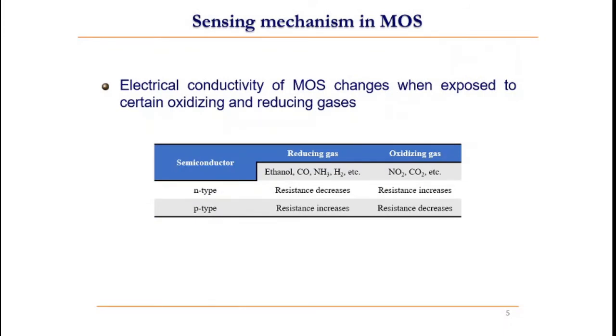When a metal oxide semiconductor is exposed to a gas, its electrical property changes. And this property depends upon the type of semiconductor. If the semiconductor is N-type and if the target gas is a reducing gas, then the resistance decreases. If the target gas is an oxidizing gas, then the resistance increases. In the case of P-type semiconductor, the resistance increases when reducing gases are present and the resistance decreases when oxidizing gases are present.